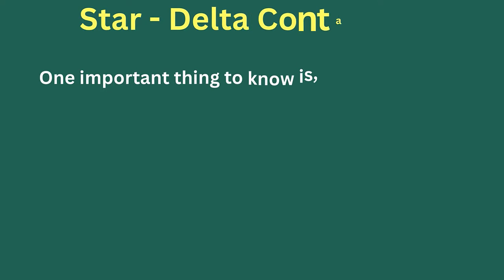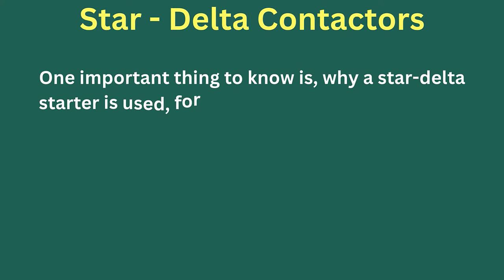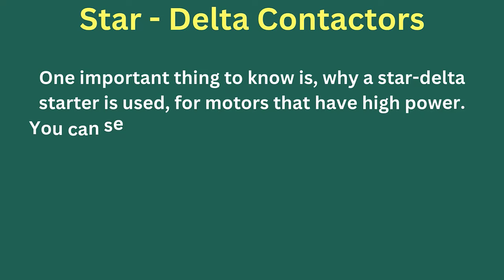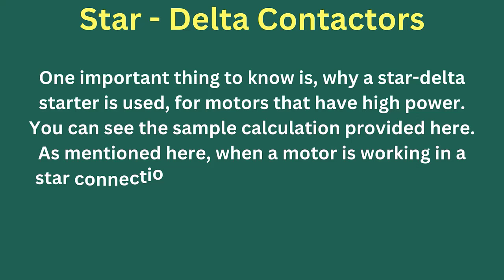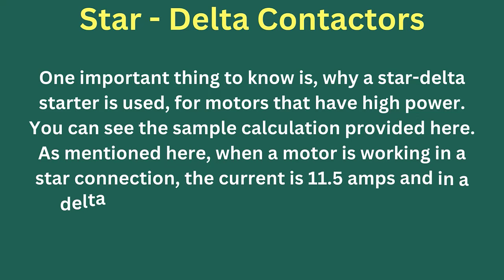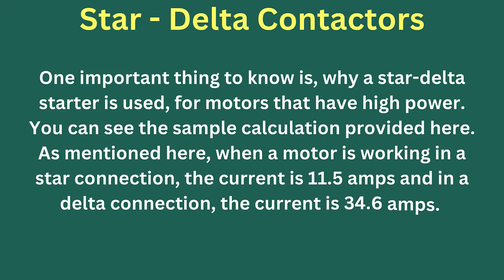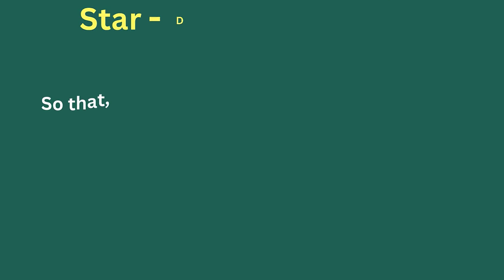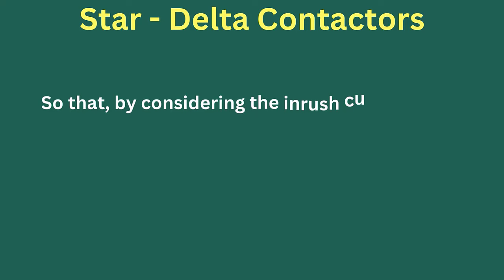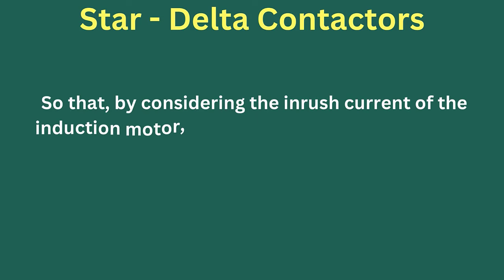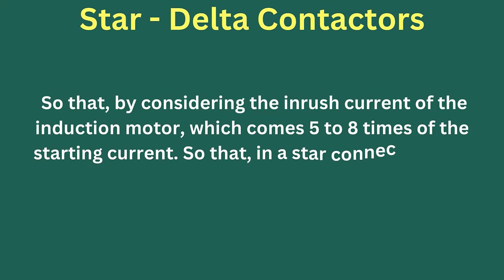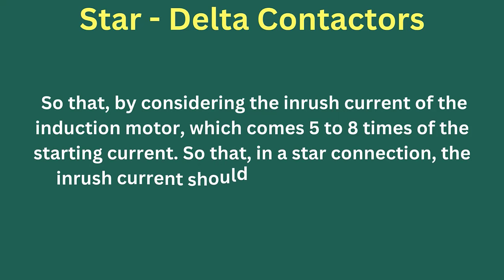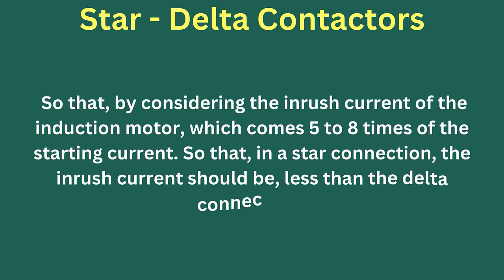One important thing to understand is why a star-delta starter is used for high-power motors. As shown in the sample calculation, when a motor runs in star connection the current is 11.5 amps, and in delta connection it is 34.6 amps. Considering that the inrush current of an induction motor is five to eight times the starting current, the inrush current in star connection is significantly less than in delta connection.